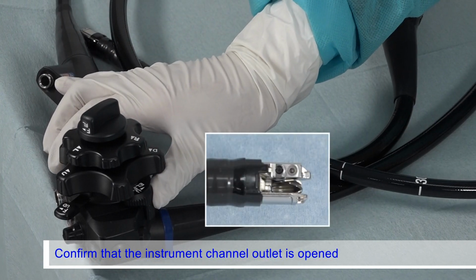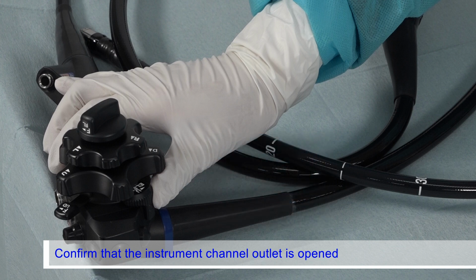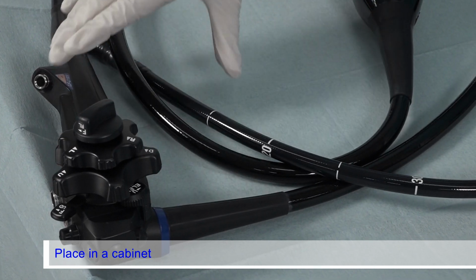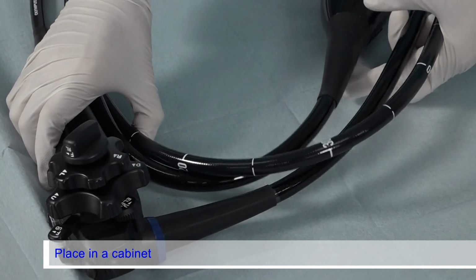Move the elevator control lever in the opposite direction of the U direction until the forceps elevator stops, and confirm that the instrument channel outlet of the distal end is opened. Store the disinfected endoscope and accessories properly.